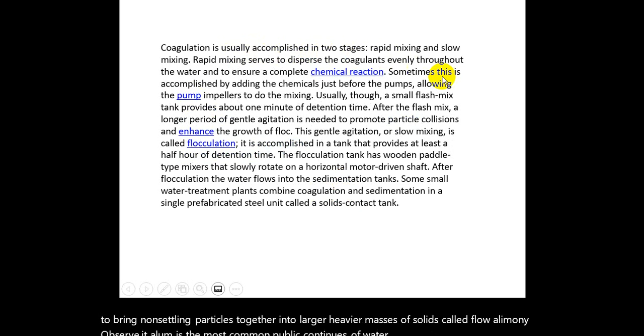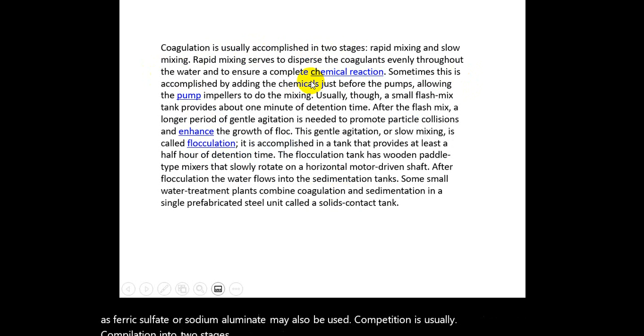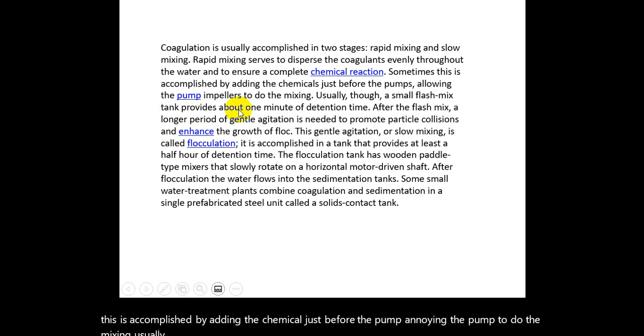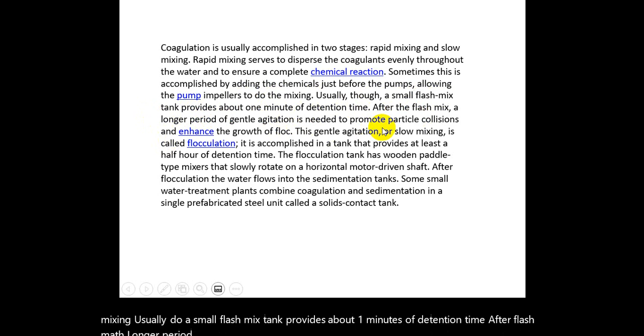Coagulation is usually accomplished in two stages: rapid mixing and slow mixing. Rapid mixing serves to disperse the coagulants evenly throughout the water and to ensure complete chemical reaction. Sometimes this is accomplished by adding the chemical just before the pump, allowing the pump impellers to do the mixing. Usually, though, a small flash mix tank provides about 1 minute of detention time. After the flash mix, a longer period of gentle agitation is needed to promote particle collisions and enhance the growth of floc.